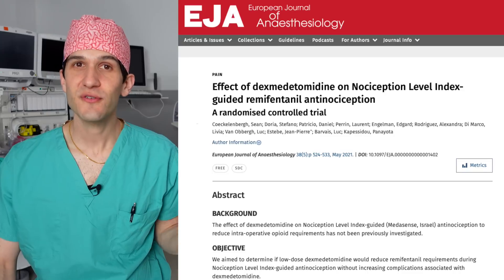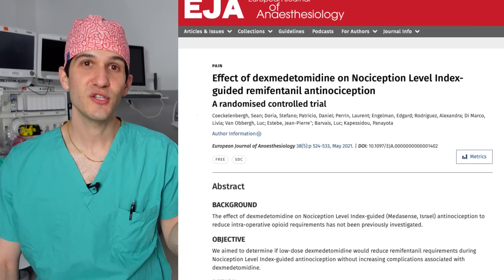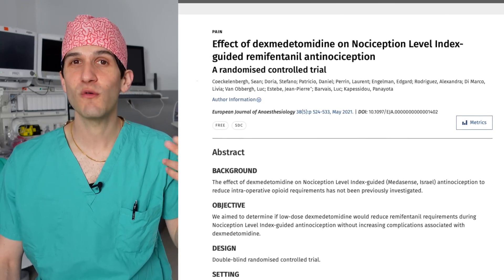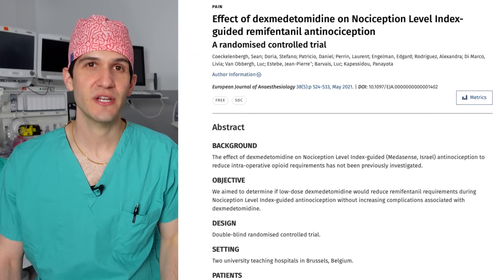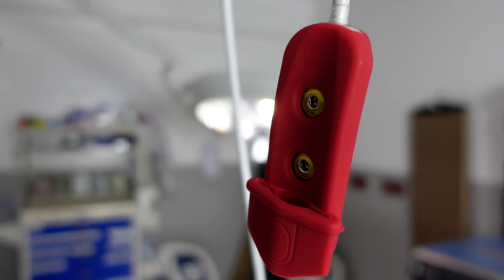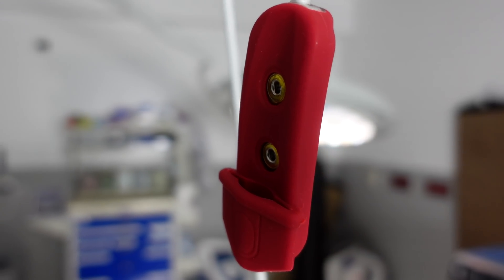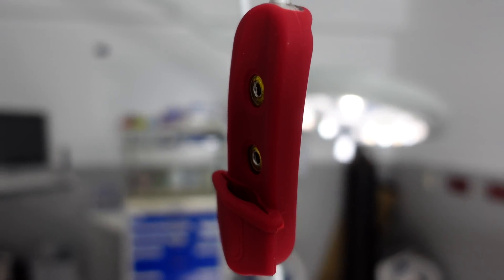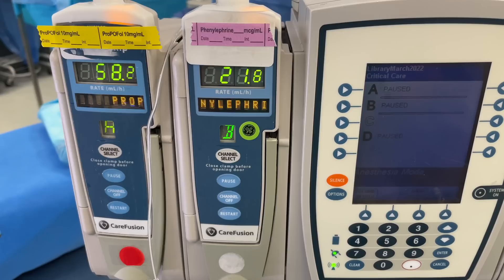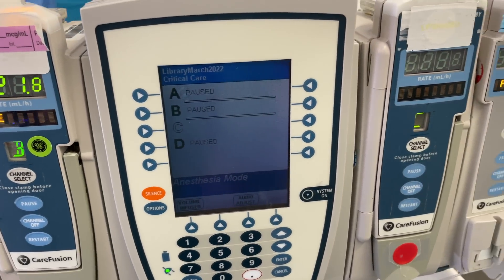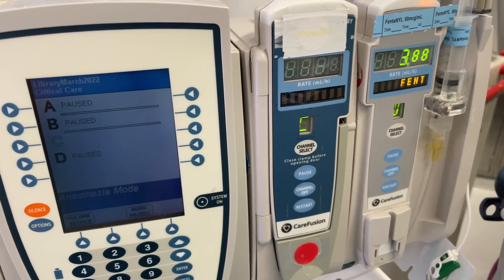The authors suggest that giving opioids at the right time during surgery — as detected by this device — contributed to improved post-operative pain scores. Another study looked at whether use of this device resulted in overall less administration of opioids during surgery. The authors found that opioid infusion rates were about 50% higher in the group that did not have this device used as a guide, suggesting that the device allows anesthesiologists to avoid overdosing patients and only administer what is necessary for surgery.